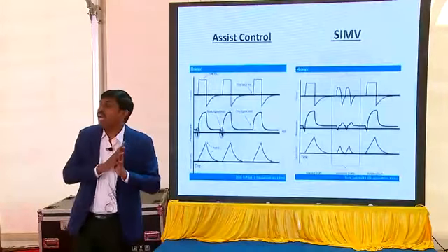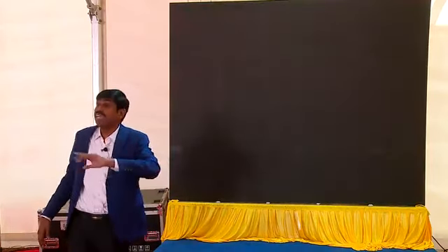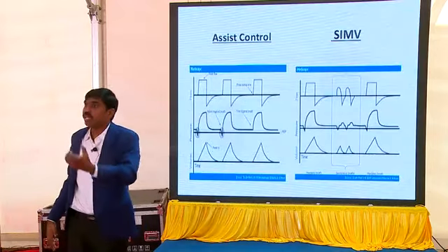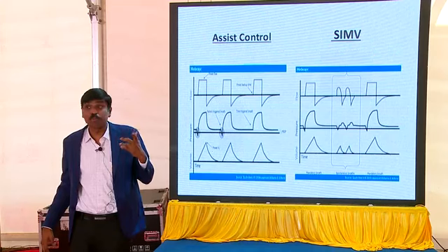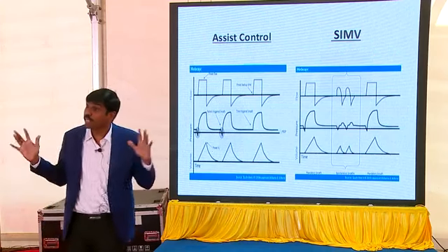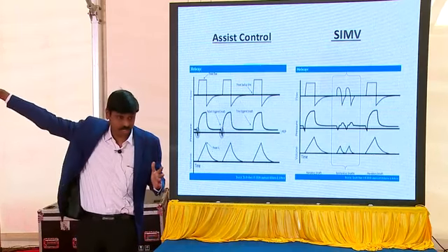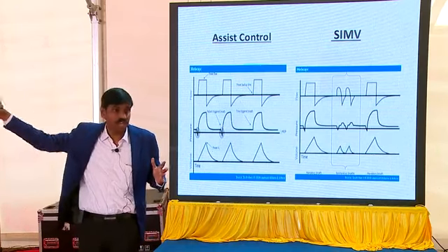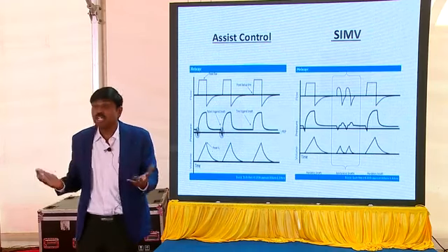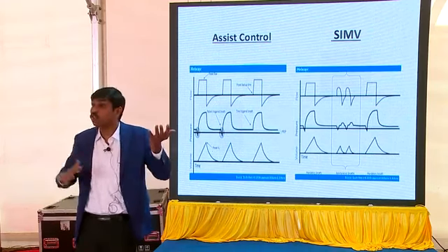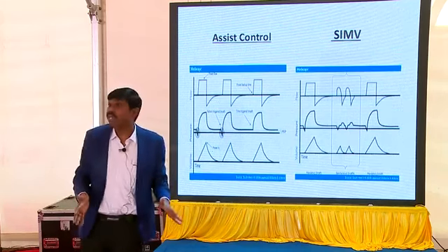Now, imagine you've got a high-volume unit where you ventilate 10 babies and you've got one nurse handling 5 babies. A lot of water condensation in the circuit there. Each movement of the water droplets would be detected as a breath by the machine. So it starts going haywire, and you will have high rates. But it's actually not the baby's breath, and your expiration is going to get lesser and lesser. Now you're going to have more and more air trapping, so it's going to be counterproductive. So that's why the senior doctor there felt that SIMV is better here.